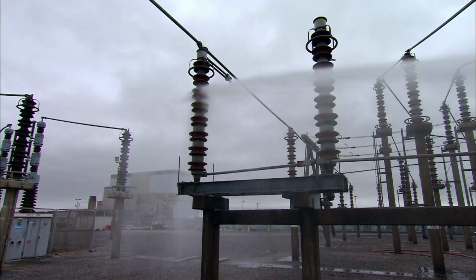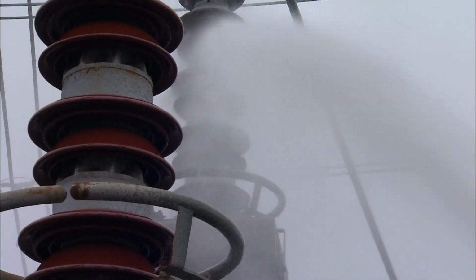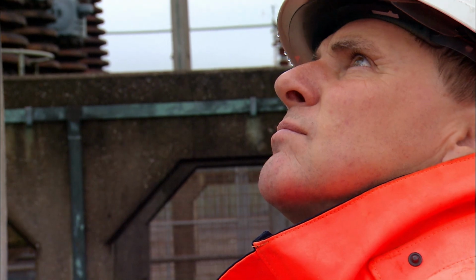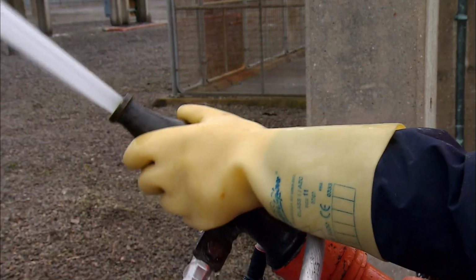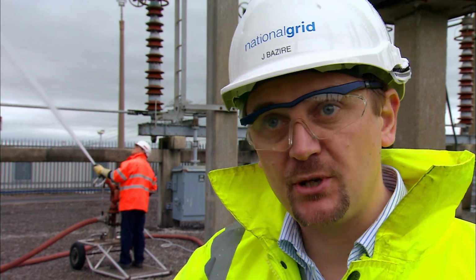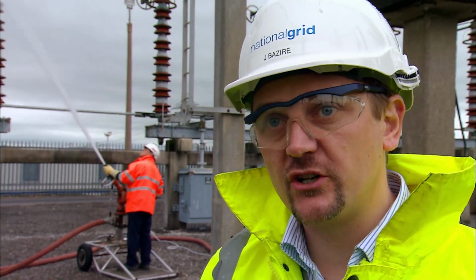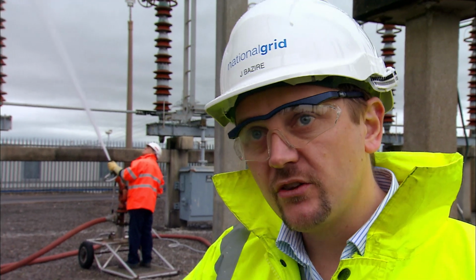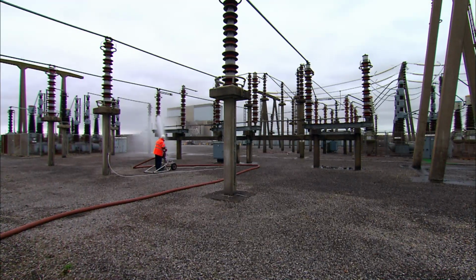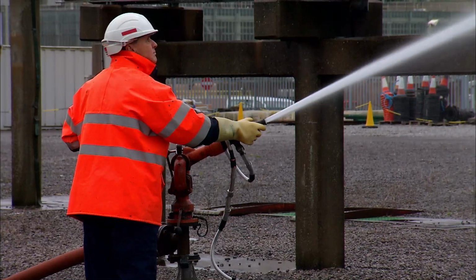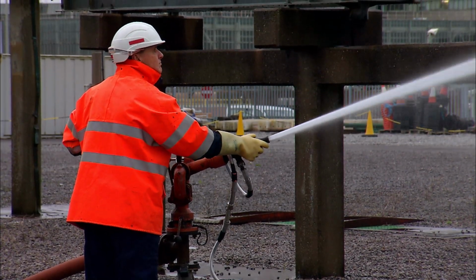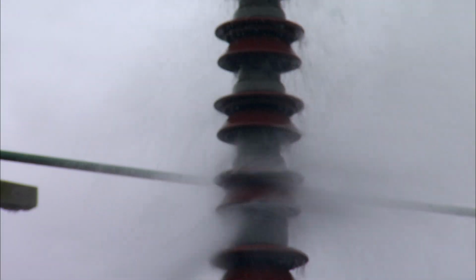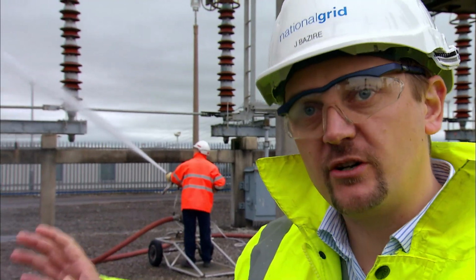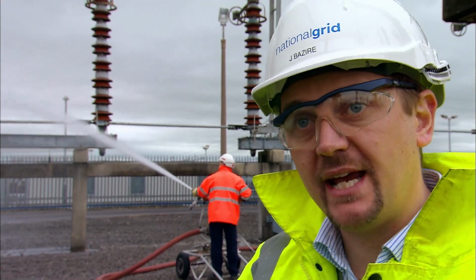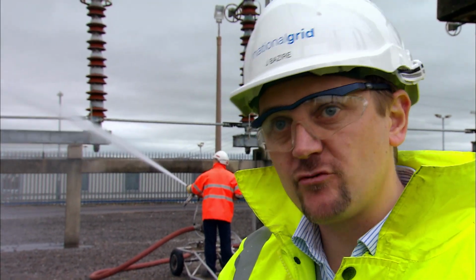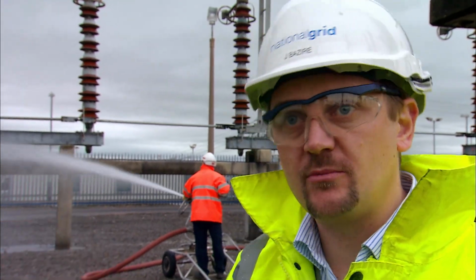The wash appears to be safely underway, but conditions can change unexpectedly. The conductivity of the water is monitored, and it's being constantly monitored. If the conductivity, that means the purity of the water, falls below a certain level and it becomes too conductive, the procedure stops. You've got a 15-second time frame. You'll get an alarm, you know then to stop washing, and the pumps will then shut down automatically. In addition to that, the pressure at which the water is delivered at 80 psi must be maintained. If that drops off, again, the whole system will shut down.